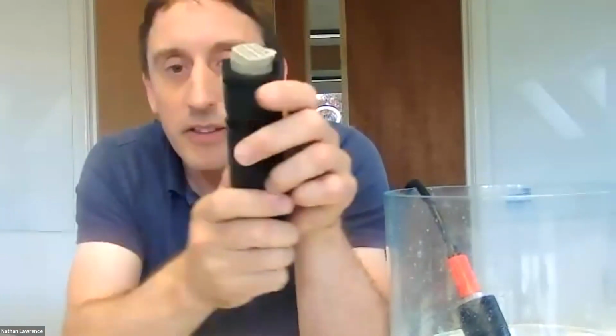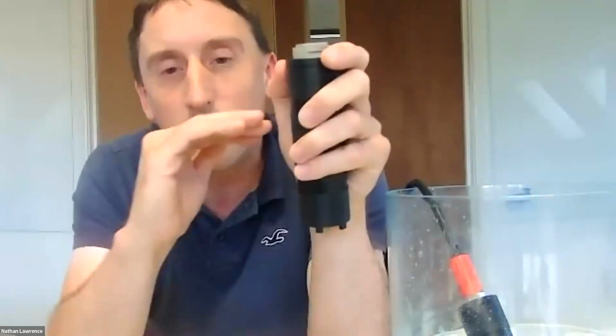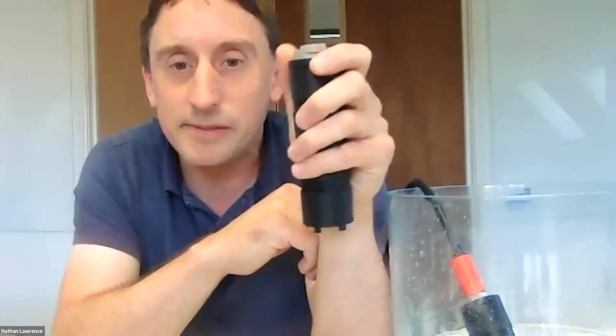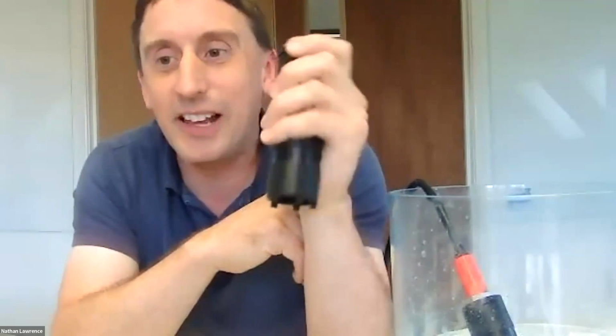It's the same with the abrasion. Unlike any glass instrument, where you have to be quite delicate, we recommend quite a hard abrasion when it's required. That's really to take off a good 5 to 10 microns off the top layer that we've got. These pellets are around 2 to 3 millimeters in depth, so they can take quite a few abrasions before they need replacing. So don't be shy with the sensor, is what we'd always say.